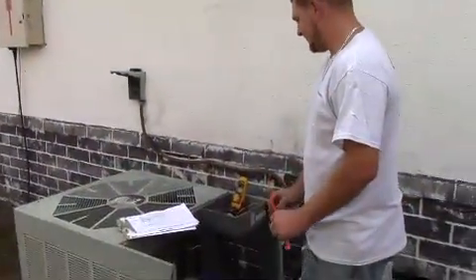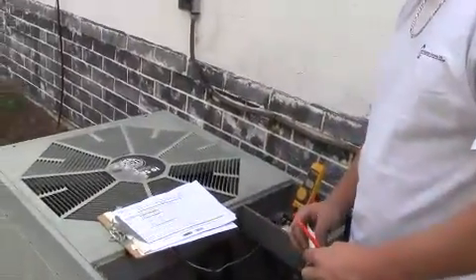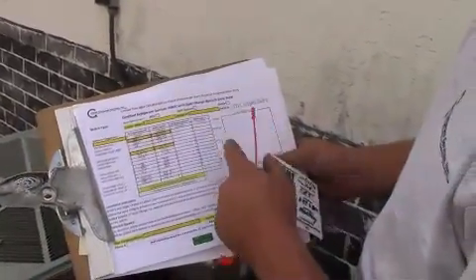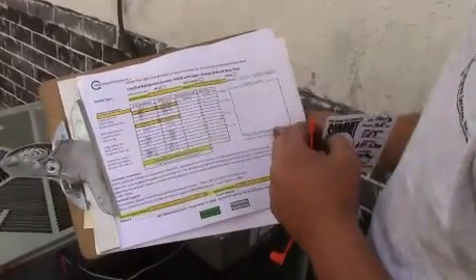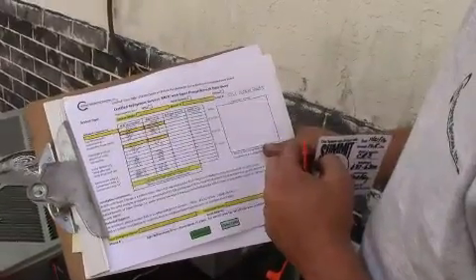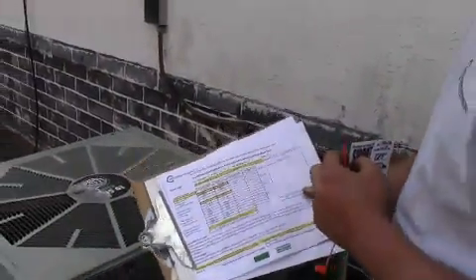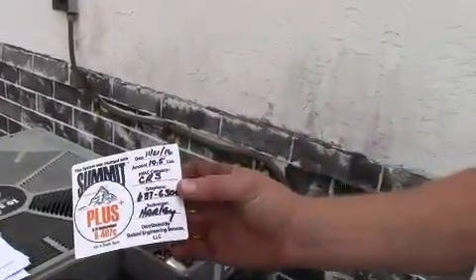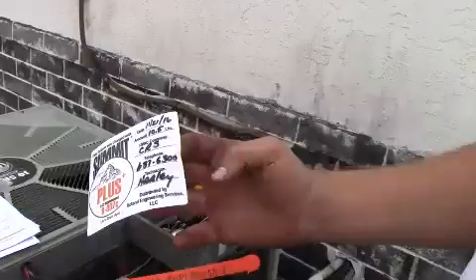Step seven is to record the data. We've got all the suction pressures, discharge pressures, superheat, subcooling, and amperages written down — a good record of the data after the retrofit. One of the things you want to be sure of is that somebody who walks up to this unit knows it has R-407C with Summit Plus. Put your label with today's date, how much refrigerant you put in, the company name, phone number, and who did it — placed somewhere visible and out of the weather.